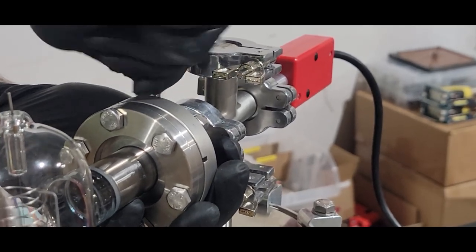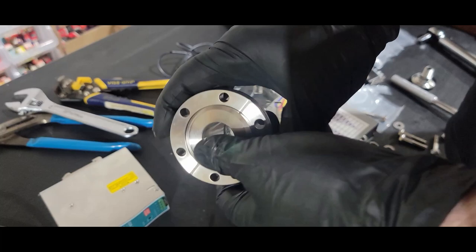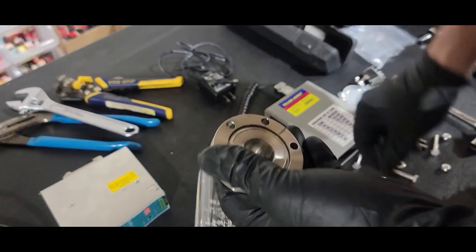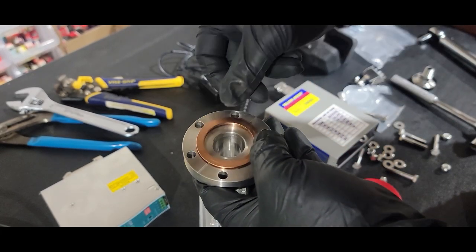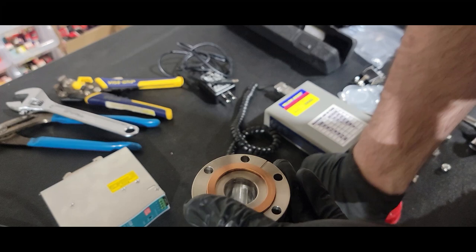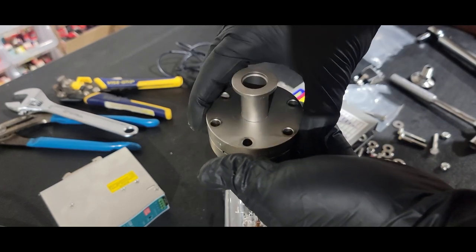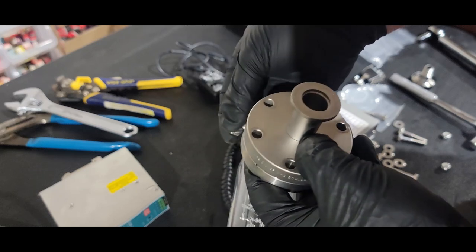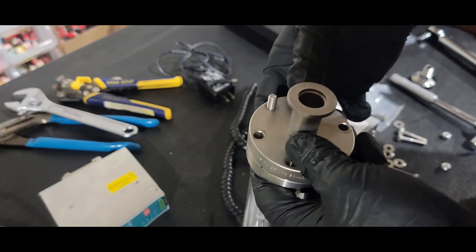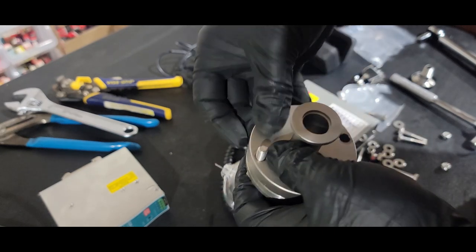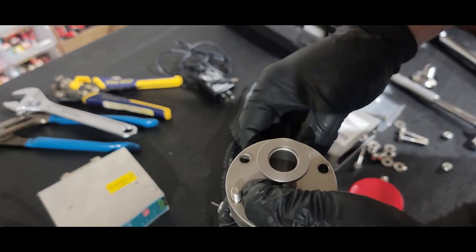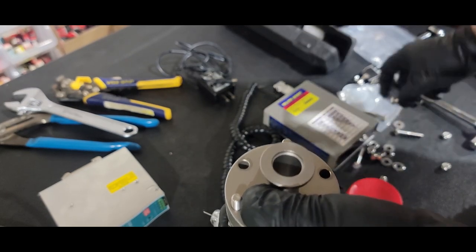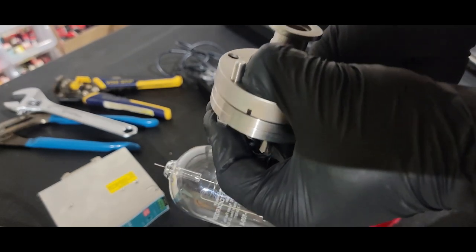The second common type of flange is the Conflat, or CF. CF flanges come in a huge range of sizes and have the advantage of being a completely metal-to-metal vacuum seal. CF fittings are bolted together with an oxygen-free copper gasket in between. Each flange has a knife edge which bites into the copper, creating a vacuum seal that can survive high temperatures and large temperature changes.